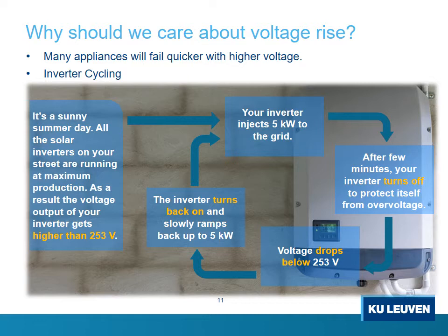Now, due to this, the reverse power flow will reduce and the voltage will drop below the maximum limit, 253 volt. Now the inverters will think that there is no problem, and then they will connect again, and your inverter will inject 5 kilowatt again to the grid. Then the voltage will get higher than 253 volt, and the inverter will disconnect to protect itself. So your inverter will keep disconnecting, connecting, disconnecting, connecting. If the inverter spends the lunchtime cycling on and off and reaching high voltages, then your inverter won't last long. Also, when the inverter is off, your solar system is not generating energy. And when your solar system is not generating energy, you are losing money.